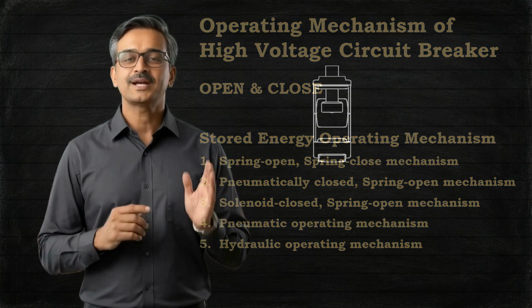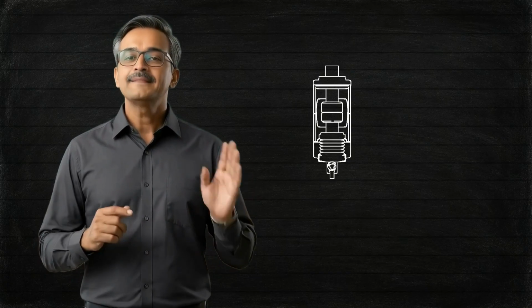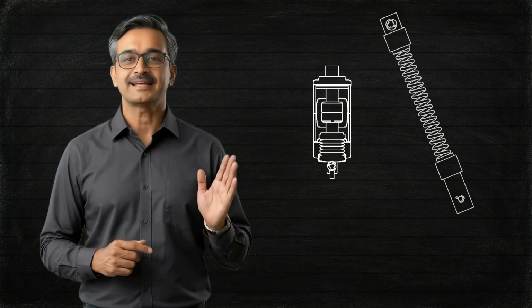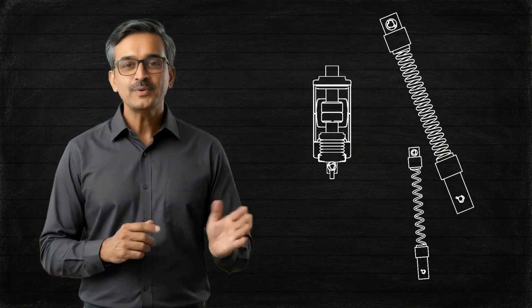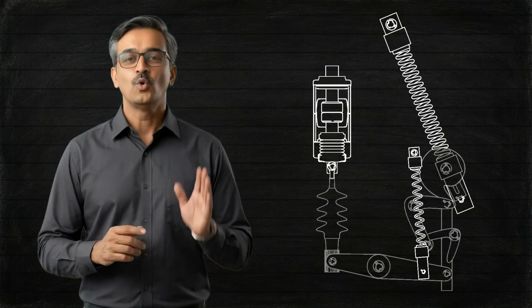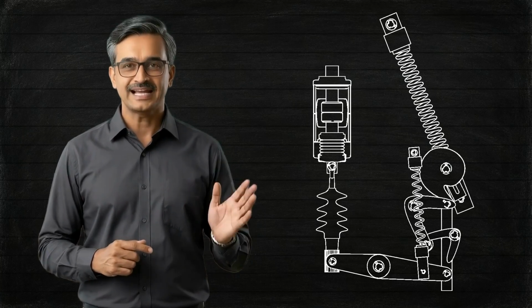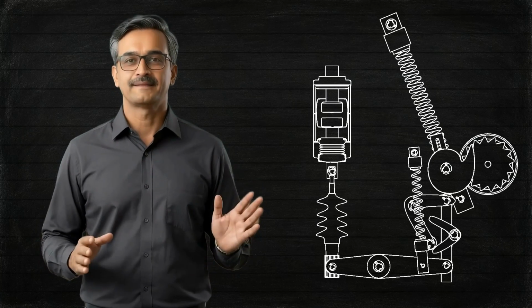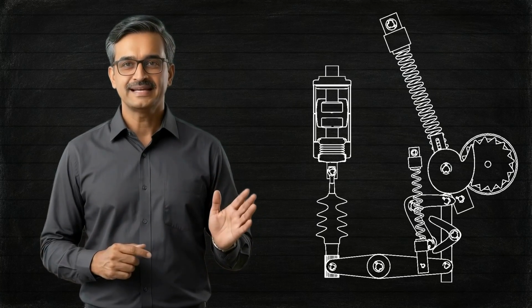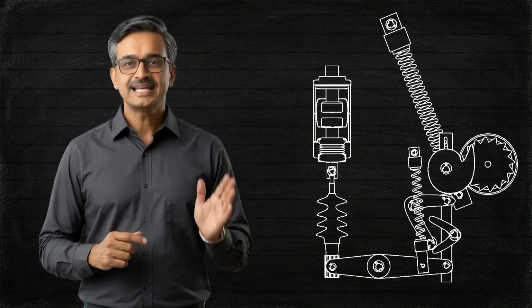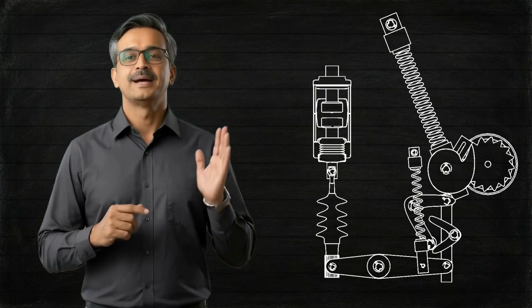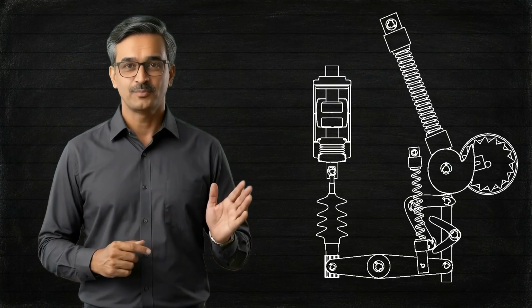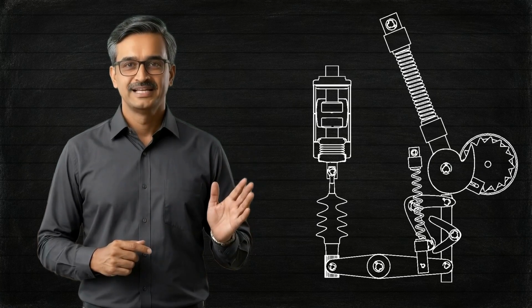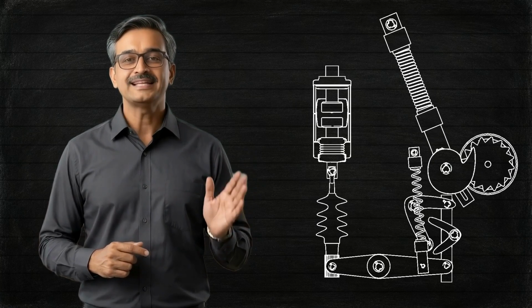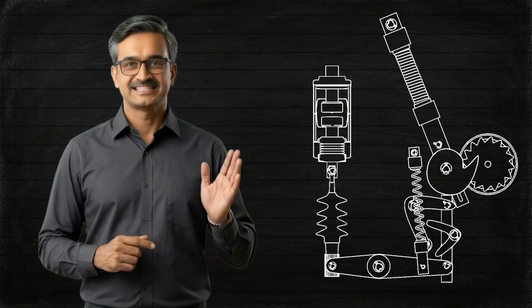First, we draw the breaker contacts. This is the fixed contact and this is the moving contact. Next, we draw two springs. This is the closing spring. This is the opening spring. Now we draw an electric motor connected to the closing spring through a gear arrangement. This is the motor. Now let us understand how it works. Initially, the motor rotates. Through the gear arrangement, it compresses the closing spring. At this stage, no switching operation takes place. The breaker is simply storing mechanical energy. As long as the spring remains compressed, the energy is safely stored.